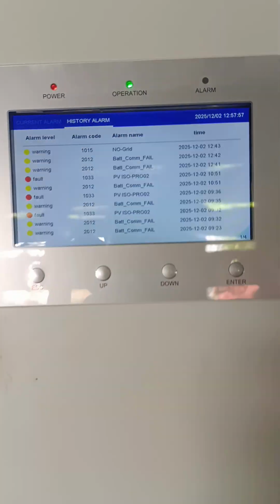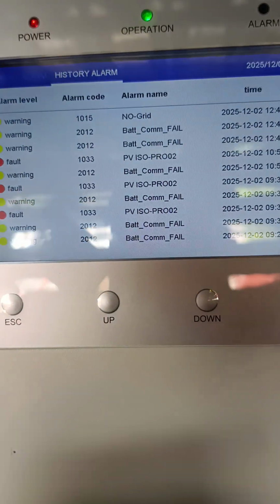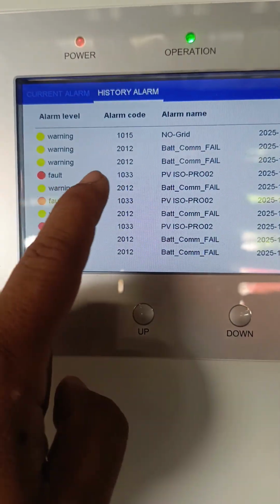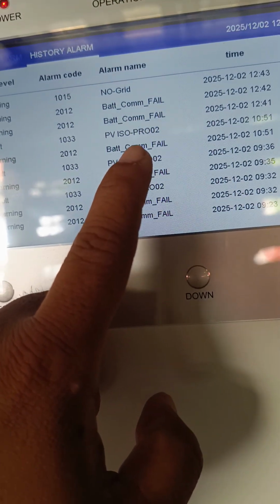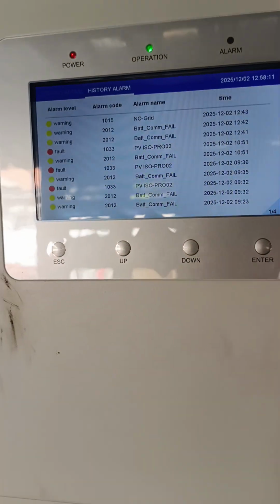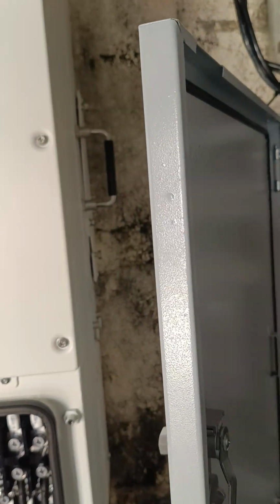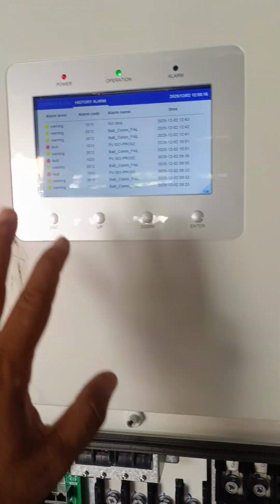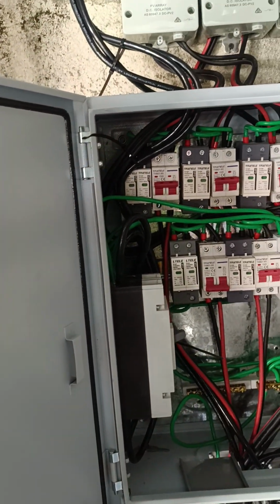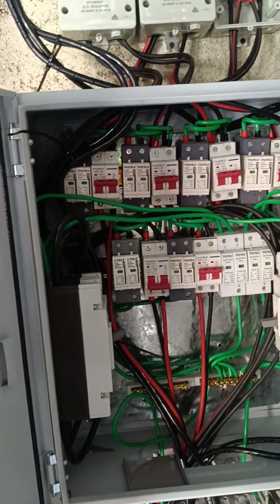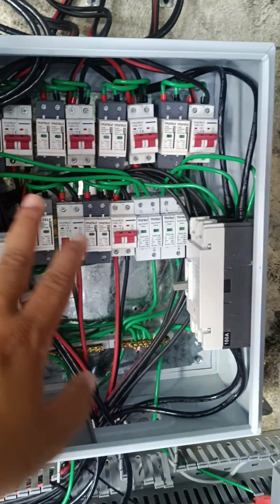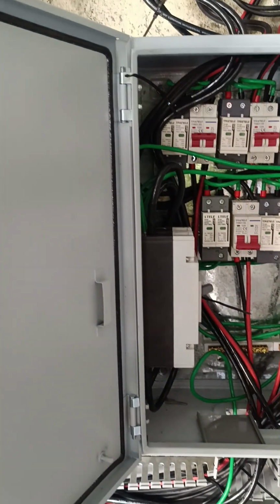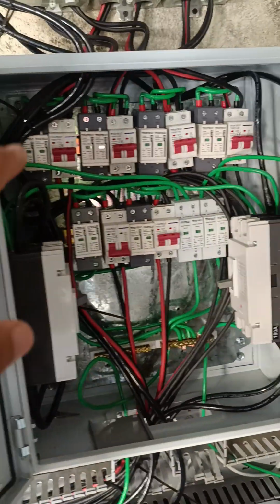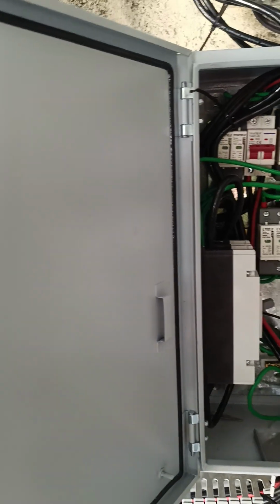Okay, we're having this issue, we have this fault with our Solis installation. Fault code 1033 PVISO Pro 02. Now what we did was first we turned off the system, all of it, and then based on our research online, we need to isolate all the PVs. Okay, turning off the PV strings one by one to detect.